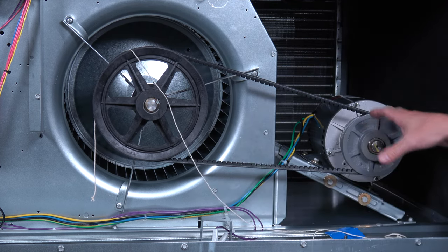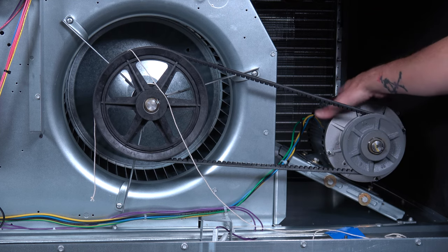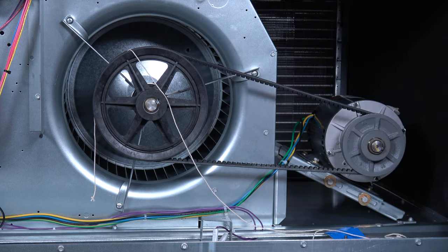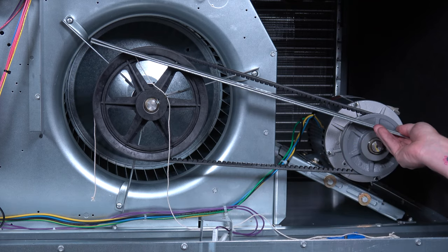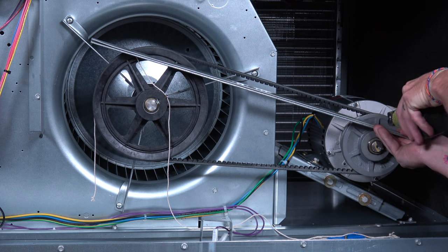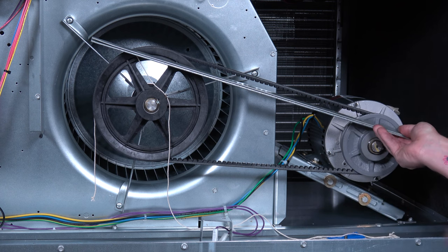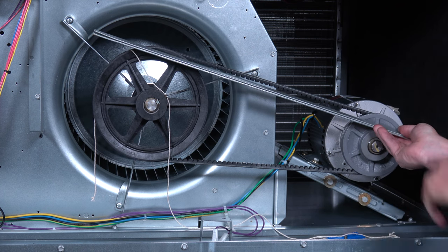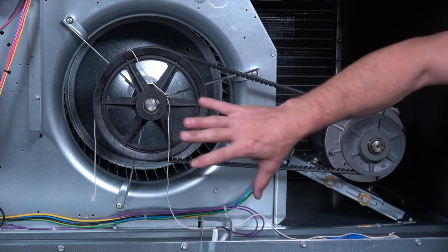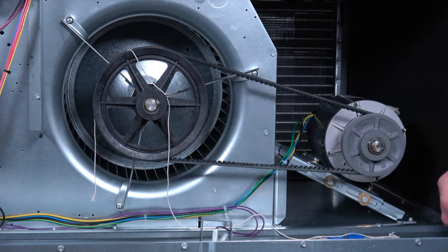The next thing I want to check is to make sure that my motor isn't turned or cocked on an angle, and that it's straight and parallel to the fan pulley. To check my alignment, I'll take two simple measurements off my motor sheave. Since they're equal distance apart, I know my motor is lined up right and that my pulley — which I can slide in and out — is what's causing my out of alignment.